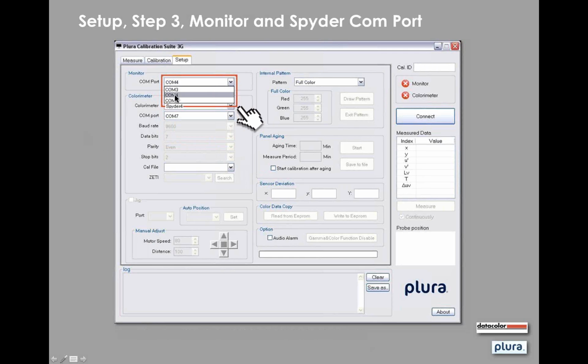And we're going to select the COM ports. You need to select the COM ports for two devices: first for your video reference display, labeled monitor here, and you need a COM port for the colorimeter as well. It's going to vary from machine to machine, so there's a bit of trial and error, or if you have the expertise you can get into the operating system and look at where that device lives, depending on your operating system. There are different places you can look that up. In any event, you set up both COM ports so the software can see the hardware.